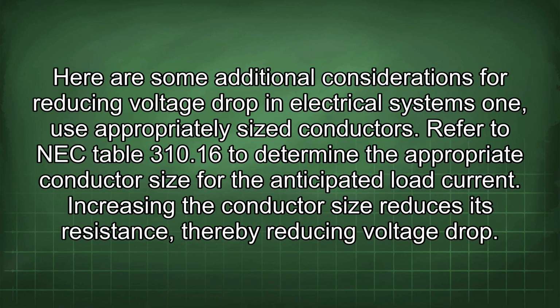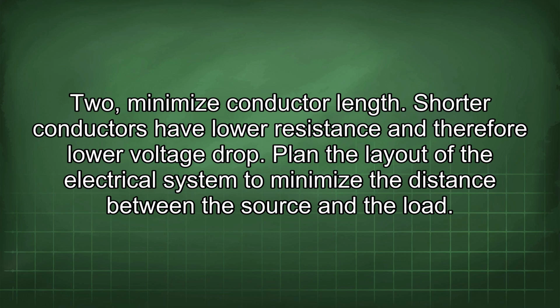Here are some additional considerations for reducing voltage drop in electrical systems. 1. Use appropriately sized conductors. Refer to NEC Table 310.16 to determine the appropriate conductor size for the anticipated load current. Increasing the conductor size reduces its resistance, thereby reducing voltage drop. 2. Minimize conductor length. Shorter conductors have lower resistance and therefore lower voltage drop. Plan the layout of the electrical system to minimize the distance between the source and the load.